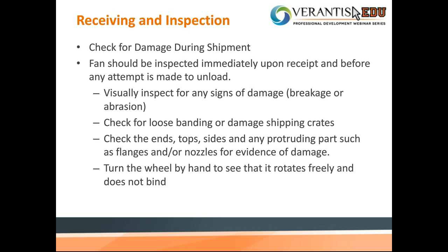Specifically for a fiberglass style fan, you should look for impact damage, where there is whitening of the surface or a star-shaped crack or crazes have occurred. This damage may be contained just to the exterior and could be superficial, but it's still worth noting. And then before you take anything out of the crate, turn the wheel by hand and see if it rotates freely and isn't bound up. If it doesn't rotate freely and it is bound up, you may have an issue where the impeller has shifted during the shipment, or the actual shaft may have gotten bent of some sort.